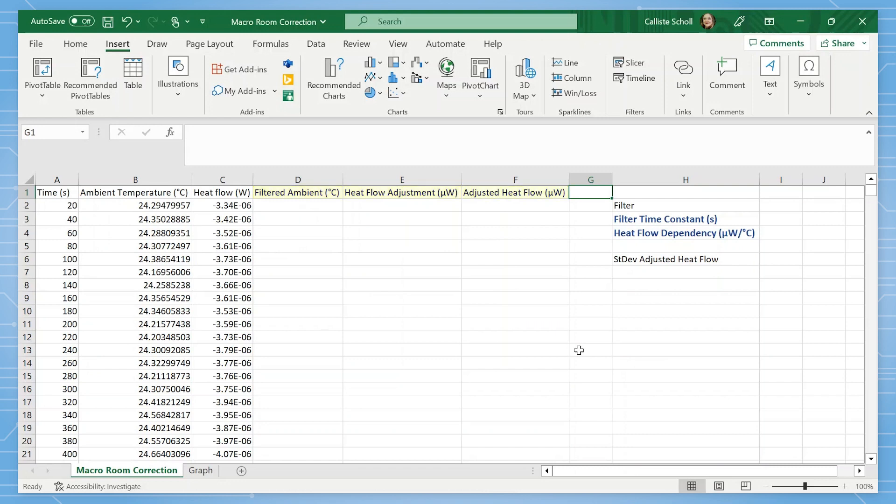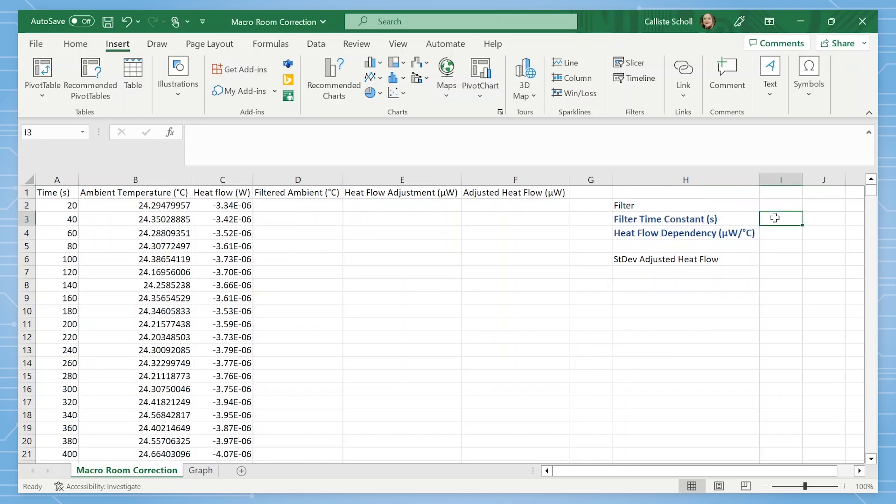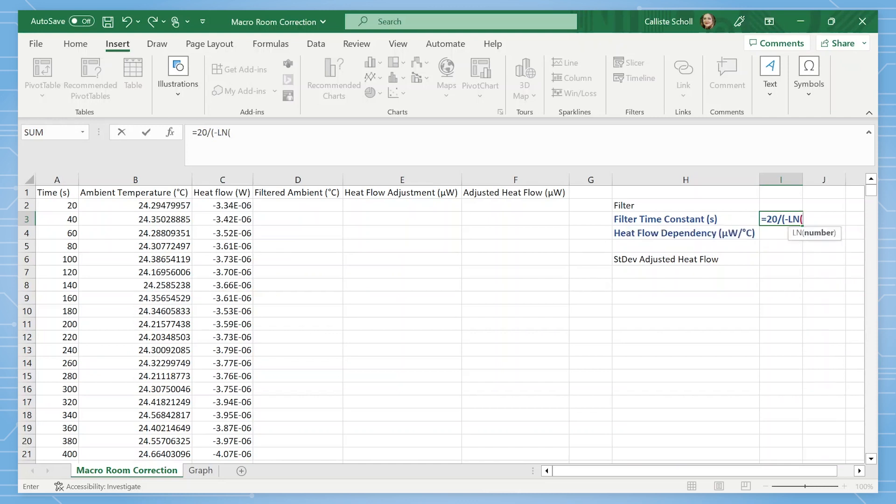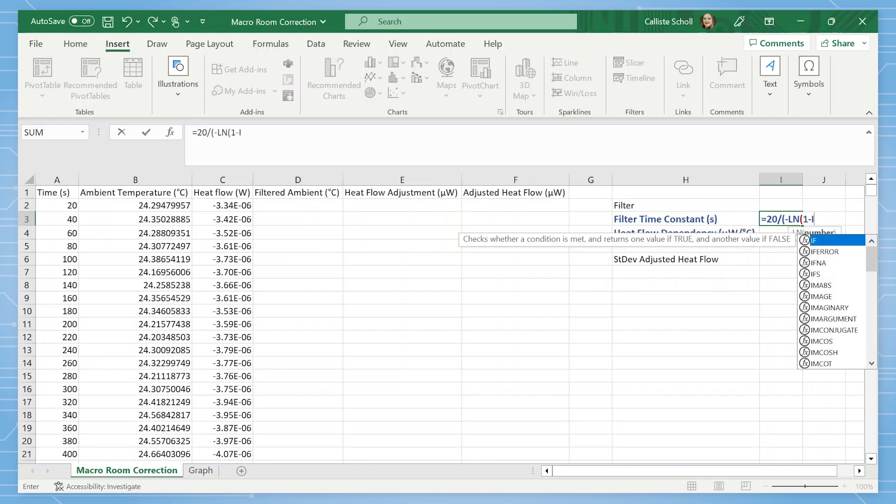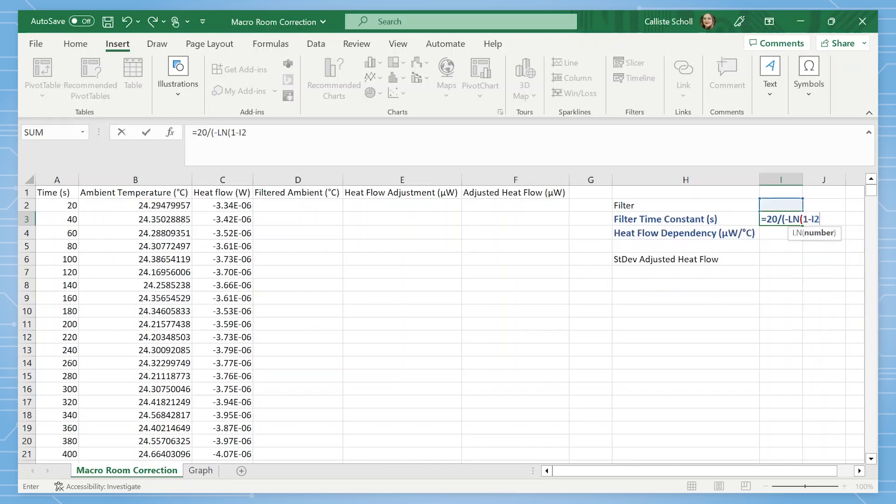We will also include the values we will be solving for: filter and filter time constant. We are solving for the filter value, which we will need to convert into a time constant. The time constant represents the thermal connection between the ambient temperature and the calorimeter measuring cup. For this conversion, the time constant is equal to the time interval, in this case 20 seconds, divided by minus ln of 1 minus filter value.